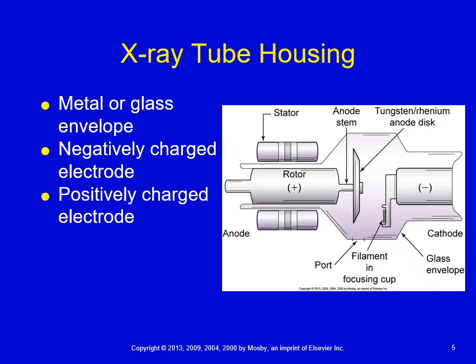All right, another purpose of the housing itself is to hold high voltage wires. Again, this particular picture does not show us a picture of the housing, but if you look in your book or just Google a picture of the tube housing, you'll see that there are two receptacle ports at the top, and those ports are where the high voltage wires hook in.